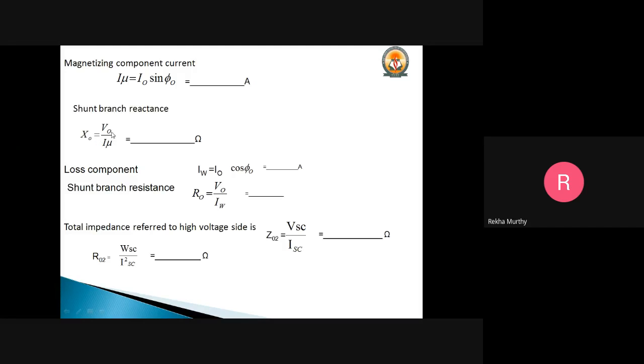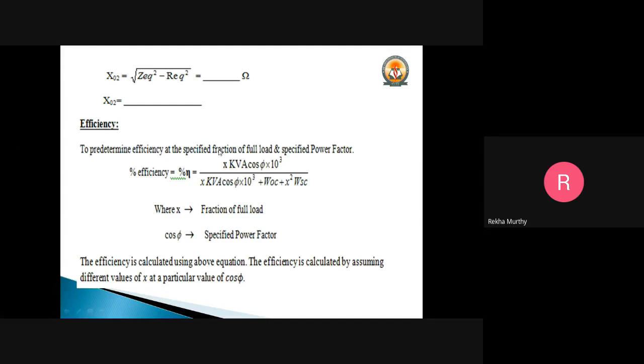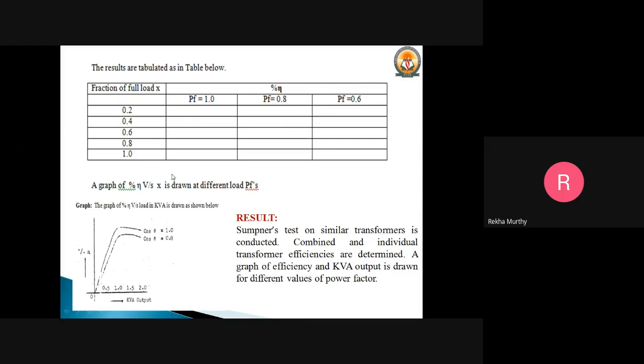The shunt branch reactance is X0 = V0 / Iμ, and the shunt branch resistance is R0 = V0 / IW. The total impedance referred to the high voltage side is Zeq = VSC / ISC. The equivalent resistance Req = Wsc / Isc², and the equivalent reactance Xeq = √(Zeq² − Req²). These values are used to calculate efficiency for different fractions of load: 0.2, 0.4, 0.6, 0.8, and 1.0, and for power factors of 1, 0.8, and 0.6, which are then plotted as a graph.